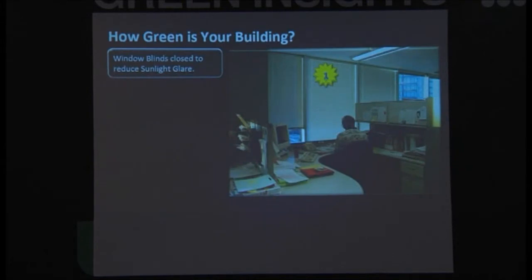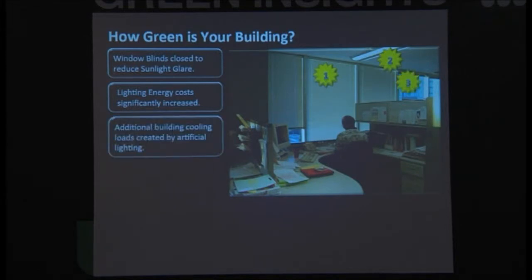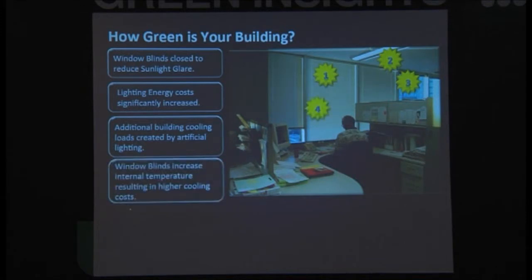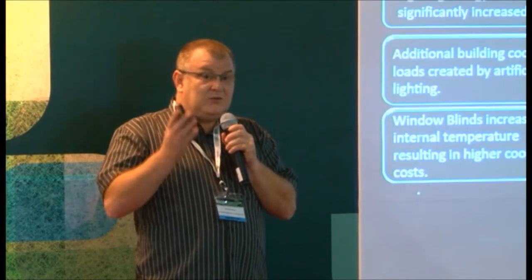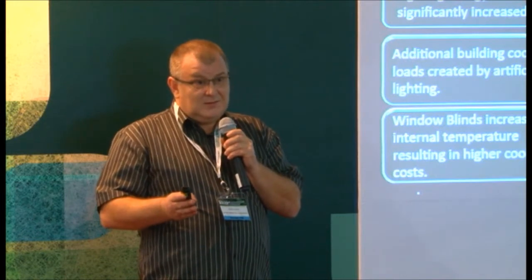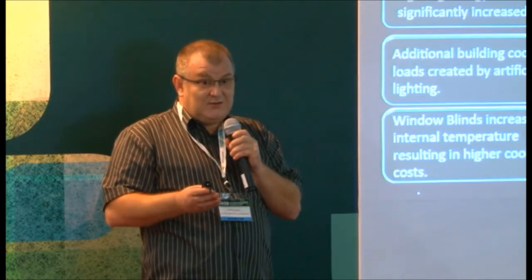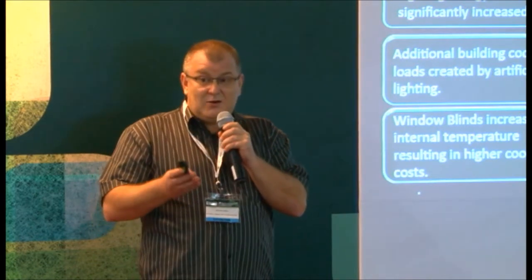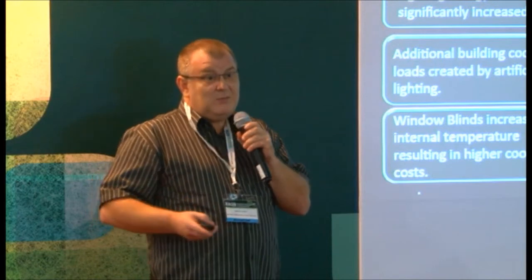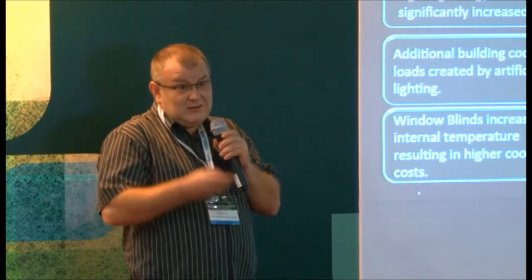So we closed the window blinds to reduce the glare because the glare is the biggest problem. The lighting energy costs are increased because now we've blocked out the sunlight. So there's no point saying this fantastic window allows so many percentage of light transmittance because now we've closed the window blinds. So its percentage transmittance is zero. Additional building cooling loads are created by the artificial lighting. And the window blinds increase the internal temperature. One of the problems with window blinds in Malaysia is when we pull down the window blind, there is air trapped behind that window blind. The sun is still passing through that transparent surface, the glass, and it's warming the air. That air then gets hotter and moves into the space. So it's a bit like boiling a saucepan of water on the stove. Eventually the steam will be generated.